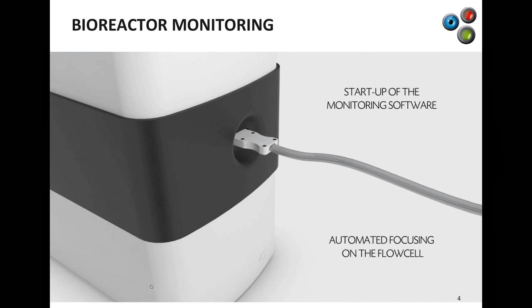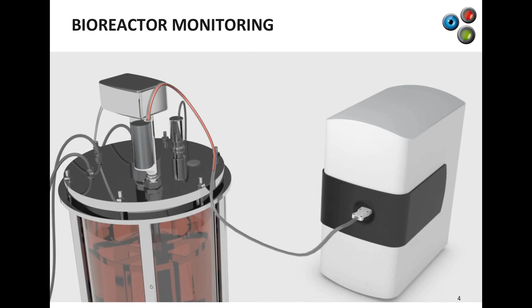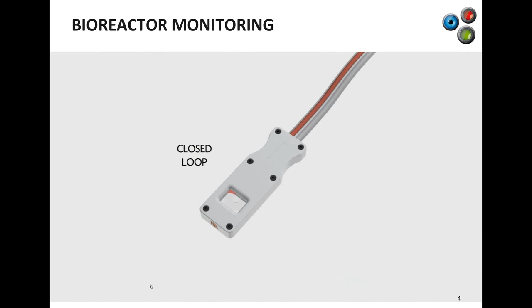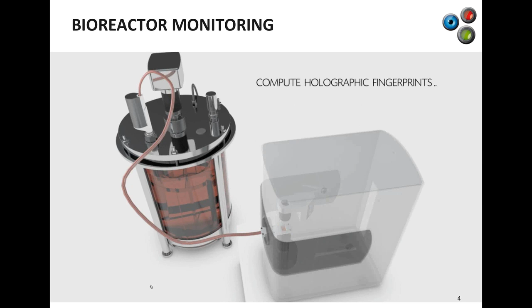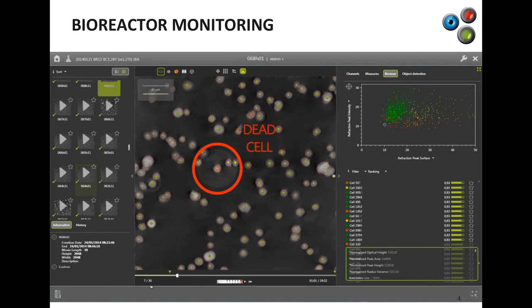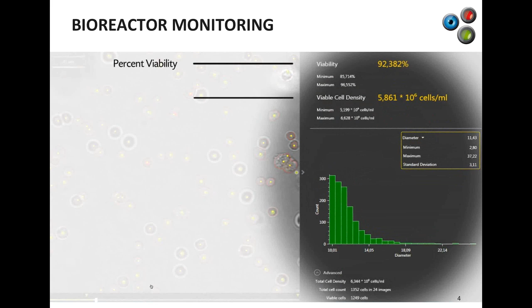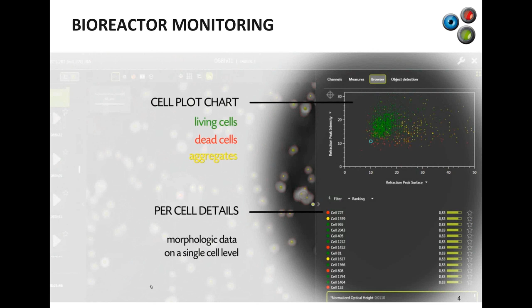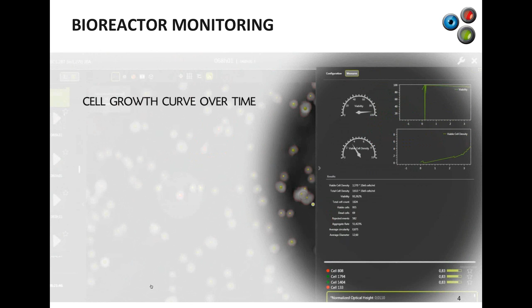From that point in time, the pump starts, and cells are pumped out of the bioreactor. They run through the reading cartridge, where the microscope will compute the cell count and cell viability based on a holographic fingerprint. This is a closed loop system, so the cells flow back into the bioreactor. We use several parameters to compute this viability, but we have benchmarked it with the current gold standards, and it gives the same results.